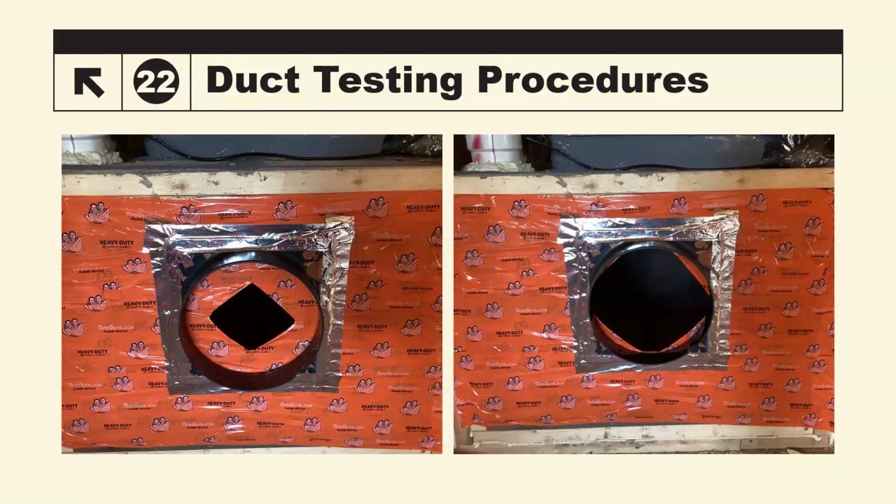Doing tape like this is basically, even though you have the fan wide open, trying to force it through a smaller hole. So if you've got TEC equipment, the one on the left is like pushing it through ring 3, and the one on the right is like having it completely open, or ring 1. So if I did a QA, I'm going to be doing it like the one on the right, not the one on the left. And I did these pictures. I actually confirmed this by doing both tests.